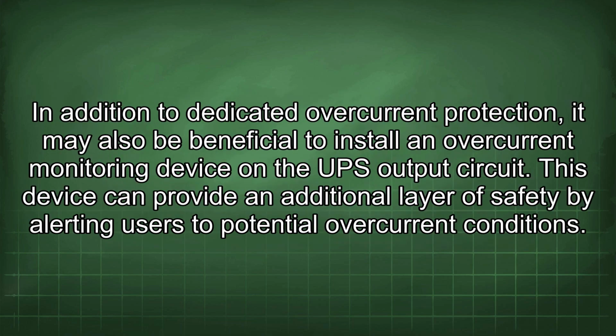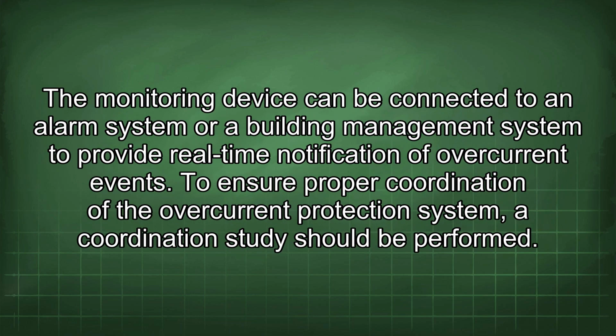In addition to dedicated overcurrent protection, it may also be beneficial to install an overcurrent monitoring device in the UPS output circuit. This device can provide an additional layer of safety by alerting users to potential overcurrent conditions. The monitoring device can be connected to an alarm system or a building management system to provide real-time notification of overcurrent events. To ensure proper coordination of the overcurrent protection system, a coordination study should be performed.